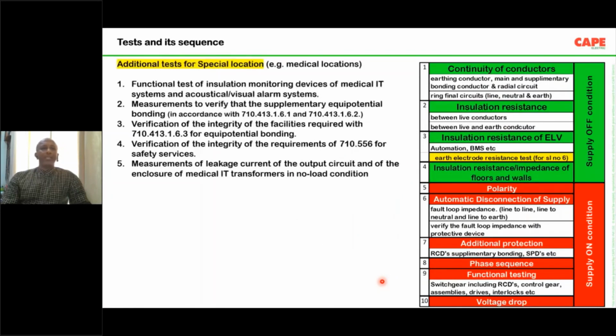Now, let us go to the tests. The additional tests which are recommended or which are made in almost every country for medical locations: number 1, functional test for the insulation monitoring device and medical IT system, and the acoustical and visual alarm system. That means you have a medical IT transformer whose secondary side is unearthed. That has to be tested. And the second test, you please read it: measurement to verify that the supplementary equipotential bonding is in accordance with these clauses of the standard. I didn't reproduce the clauses of the standard, but the supplementary equipotential bonding is the second test.